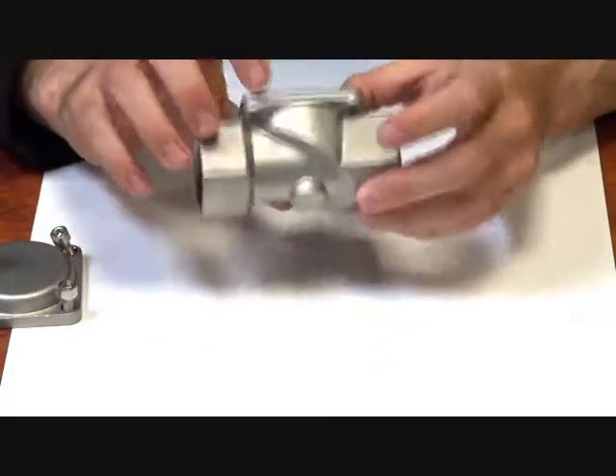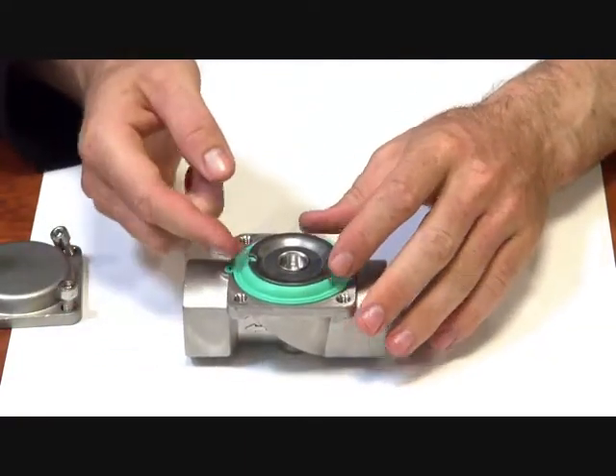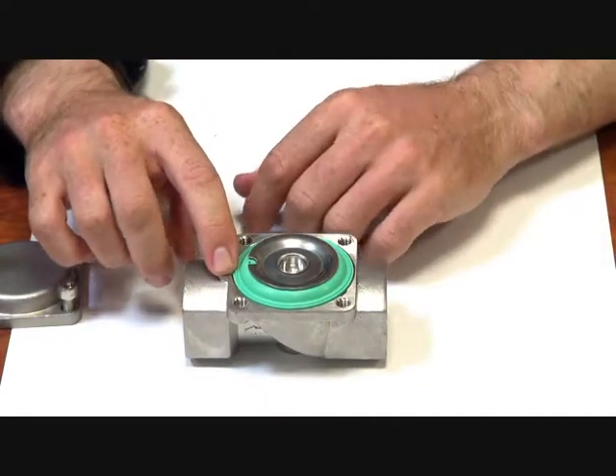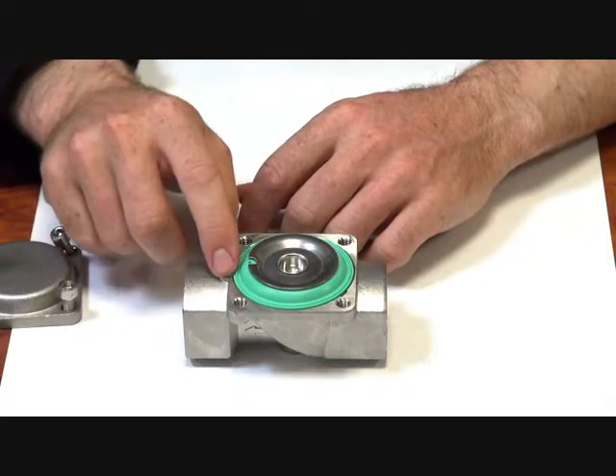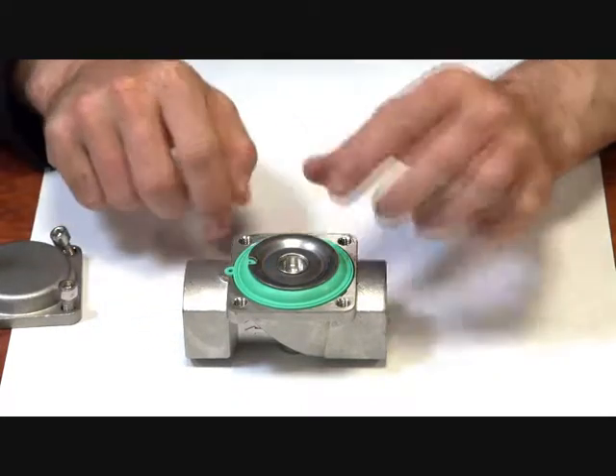You see this arrow of flow here, takes it from upstream, there's the arrow, upstream. Liquid comes around, or air, goes on top of the diaphragm. Now it can't escape because this hole is blocked off. When you actuate the valve or put power to the valve, the armature lifts up and lets the water go off down the bleed hole.